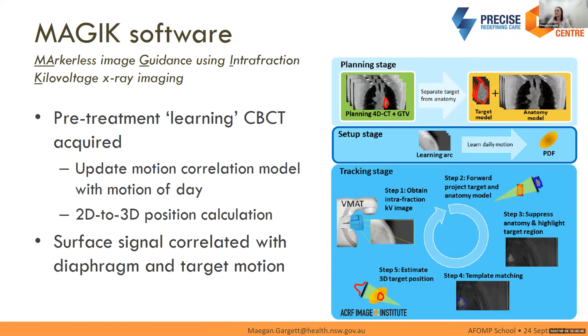So during treatment, we collect KV fluoroscopic imaging to be used as the tracking input. Each incoming KV frame undergoes some pre-processing. Then the tumour position is calculated and reported as a 3D position in the software interface. That process repeats for all frames as they're acquired, so giving us a real-time tumour position during treatment.